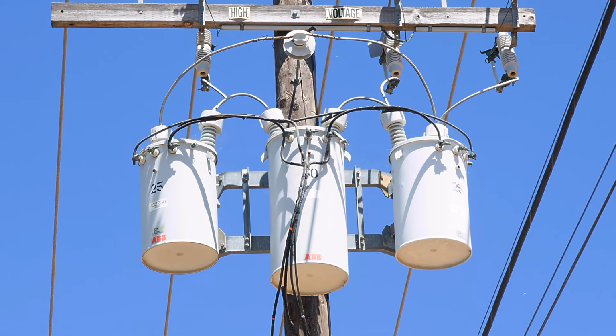You can see this delta connection here, the short jumper wire connecting the transformers on the left and the X phase lead. The line worker that put this together used a single conductor for the jumper and lead wire. The jumper on the right and the Y phase lead are constructed the same way with a single conductor. The long jumper connecting the outer transformers is connected to the Z phase lead using a crimp connection hidden under some electrical tape. And if you look close, the neutral is connected to the center tap of the middle transformer.